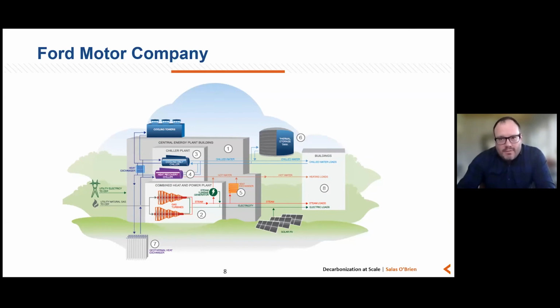This is a mix of very high temperature industrial or research needs. So there's steam use that will be maintained on this campus, but also a lot of low temperature hot water use as well. So here we're transitioning from 180-degree steam heated buildings to 120-degree hot water supply temperature for space conditioning, and doing that through a collection of right-sized heat recovery chillers, a ground source heat pump system, and then steam to hot water conversion off of cogeneration assets that are servicing a large electric load for this campus, as well as the need for steam in a collection of buildings here.